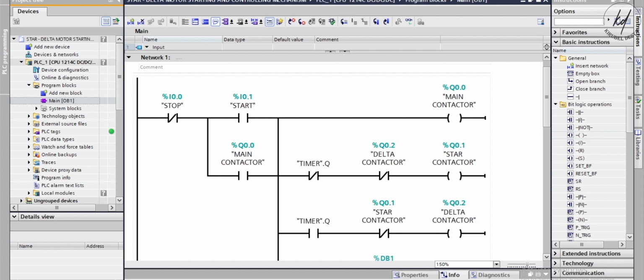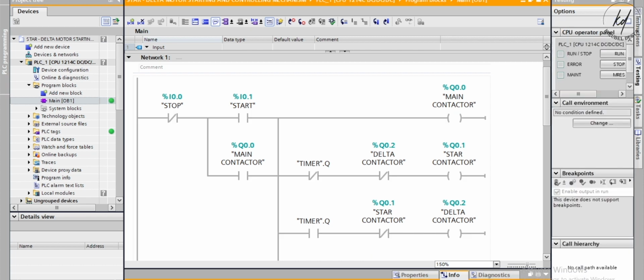Working principle of star-delta starter. The star-delta starter is most common and extensively used to start the induction motor. This is the most common reduced voltage starter. To understand the working, first we have to understand the three-phase connection in star and delta configuration.